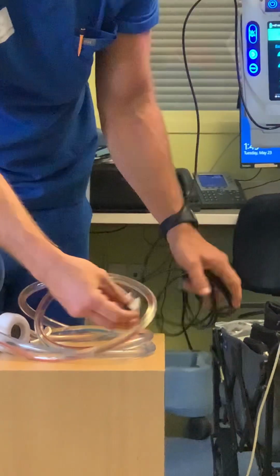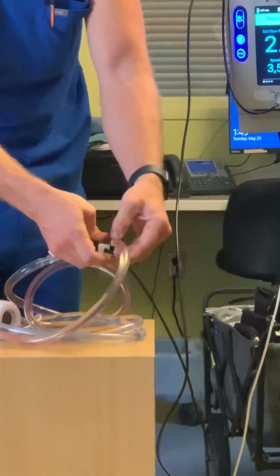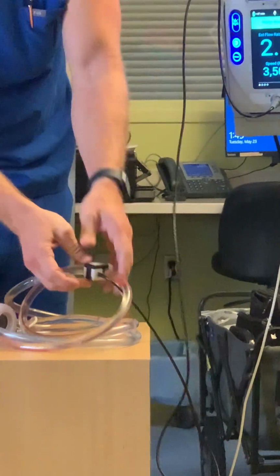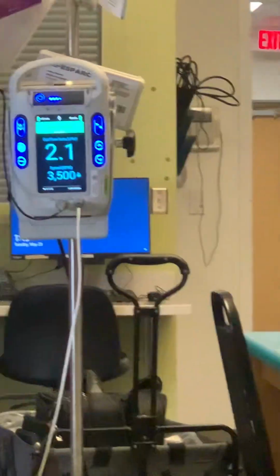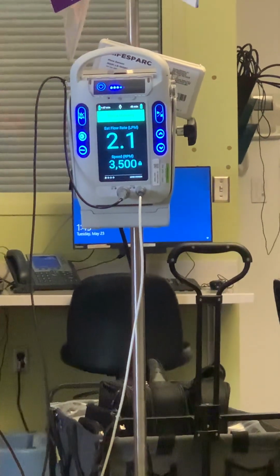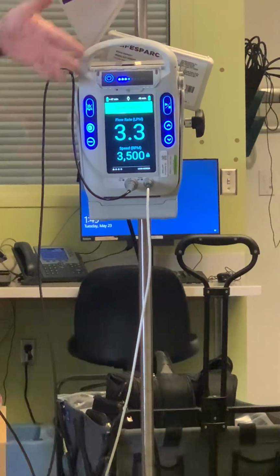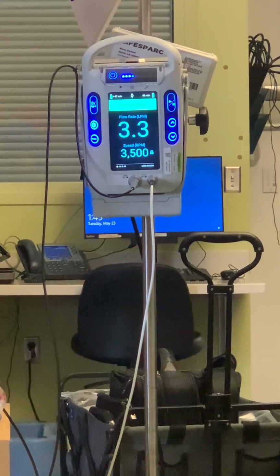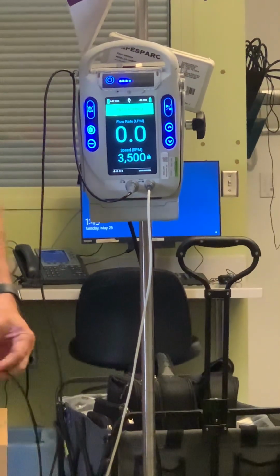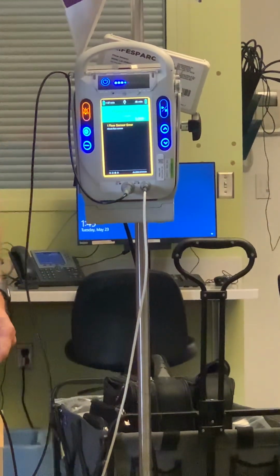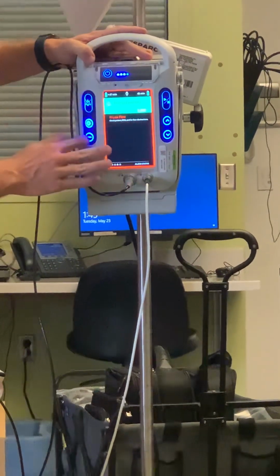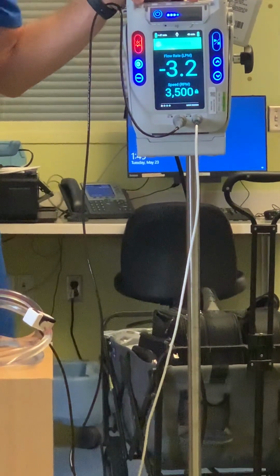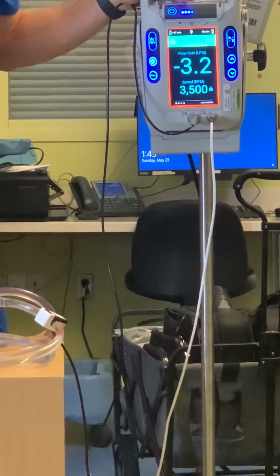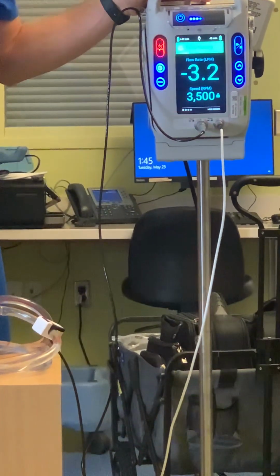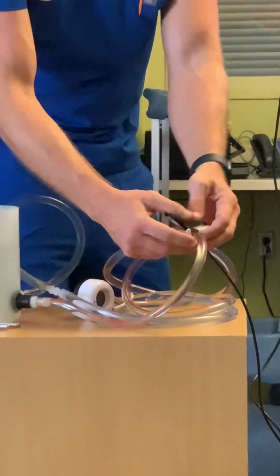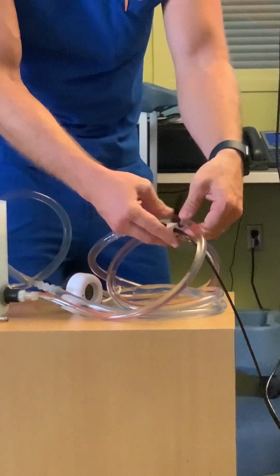Just to demonstrate, if we put it on backwards, it will read negative flow, and it will alarm at you. So we'll just plug it in here. And it takes about 5 to 10 seconds to read differences in flow. So I put it on actually the proper way. I was looking at it backwards. So it's reading negative 3.2. At that point, if you ever did see that, you would just want to verify that the physician hooked the circuit properly, but most of the time it's just put on incorrectly.